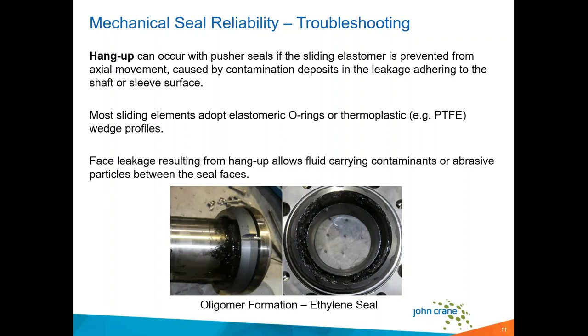Early on, it was maybe a wedge design. They're less prevalent now, but you may still come across those. In either case, those elastomer elements may hang up due to deposits or accumulation from what's coming across the seal faces.